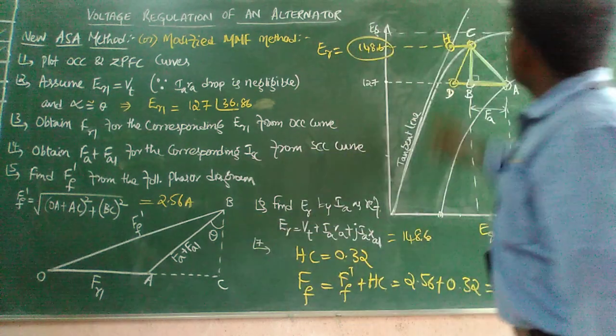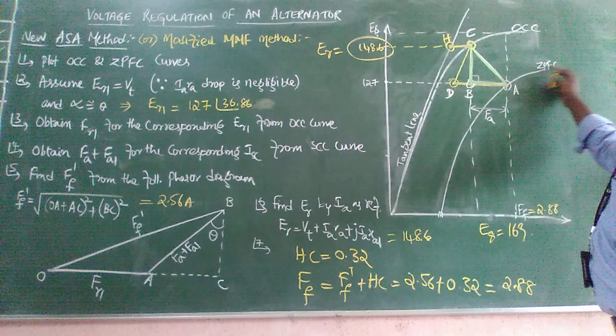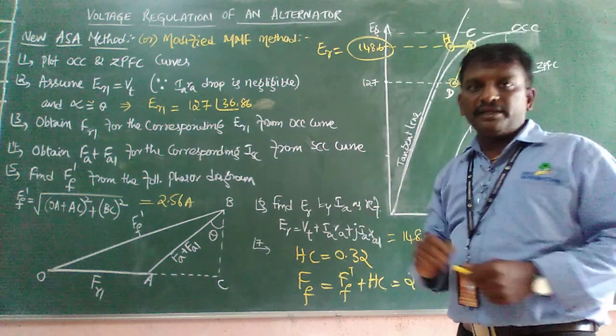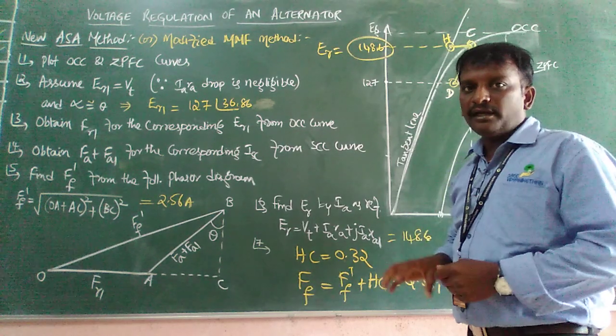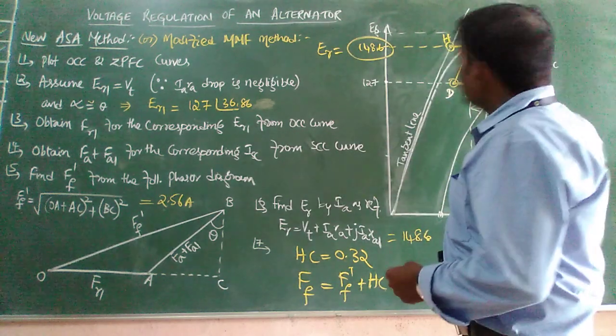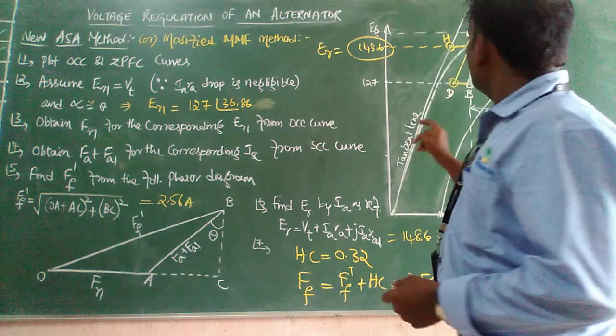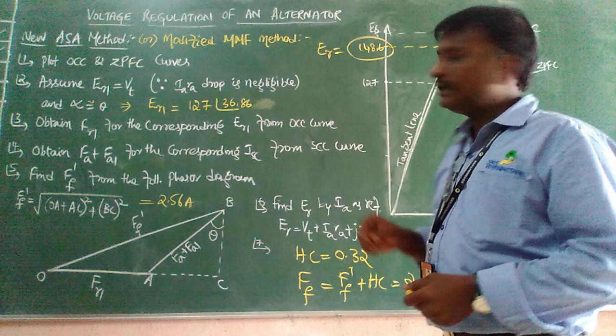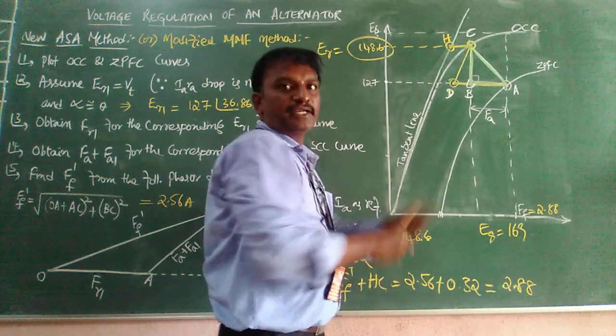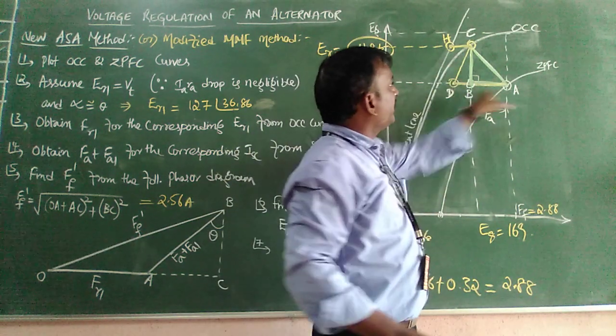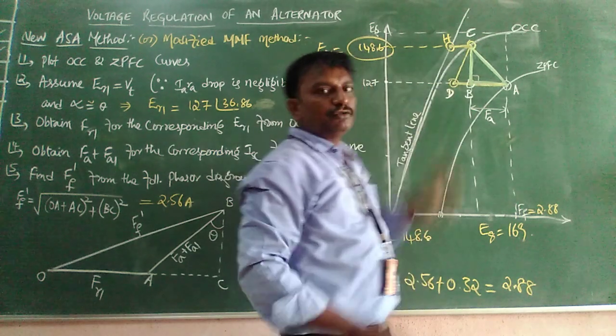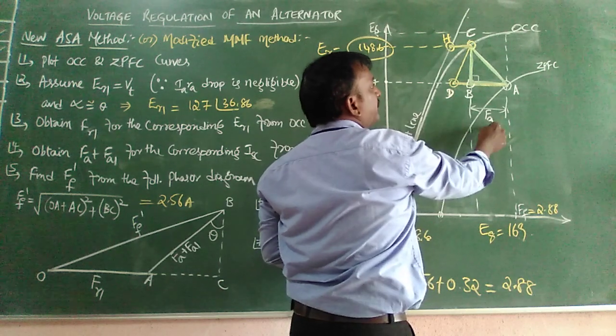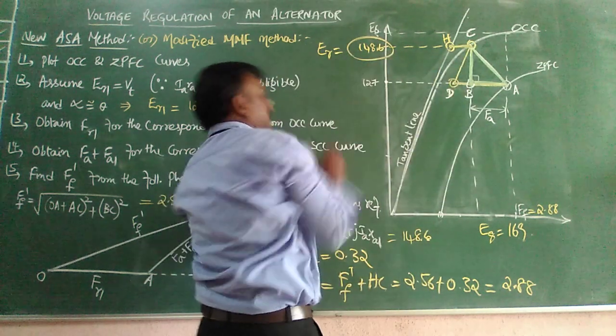By drawing these two curves — this is your OCC and ZPFC — we already know how to draw this ZPFC curve. We have the data, and based upon the data or per phase values, you draw the OCC and ZPFC. In the last class, we discussed how to construct the Potier triangle. Here is your Potier triangle ABC, where AB indicates the rotor MMF and BC indicates the IaXal drop.